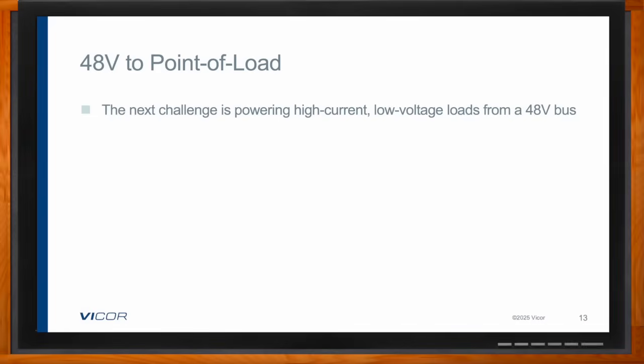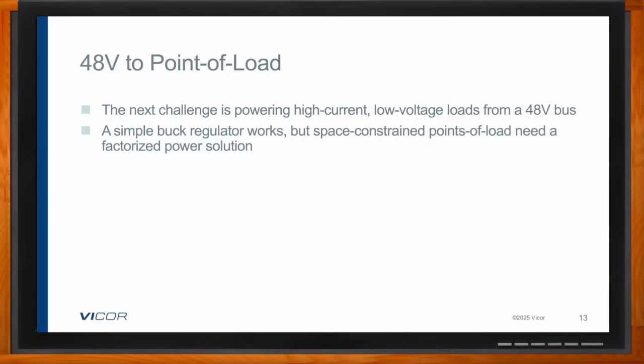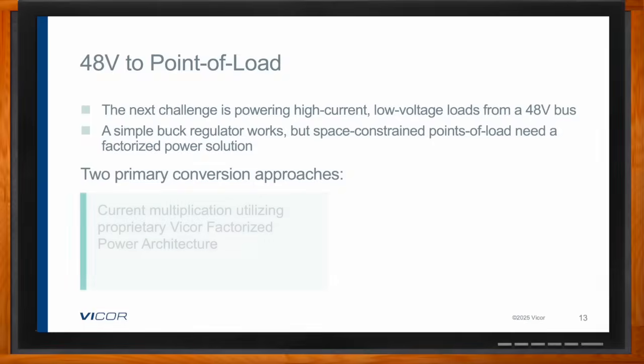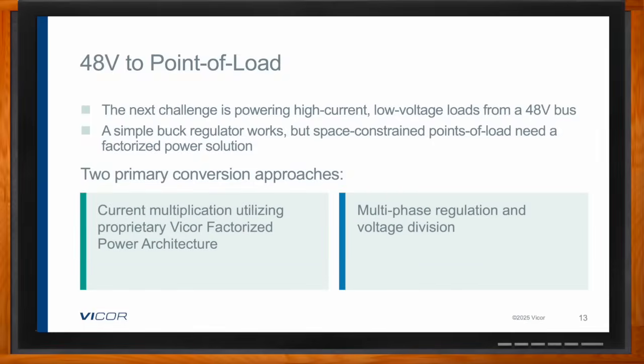Powering high current, low voltage loads from 48 volts typically requires a buck regulator. It's space constrained; points of load need a factorized power solution. So we've rethought the concept of taking a bus module and doing a non-isolated point of load approach. We've taken it to what we call factorized power architecture, where we're actually doing current multiplication at the point of load - a proprietary approach. We do the regulation upstream from this current multiplication, so it's really a new way of thinking about implementing a power delivery network. There can be multi-phase regulation, and voltage division is also occurring at the point of load. This is a new way of addressing very challenging loads, like high performance computing is a really good application to consider here.